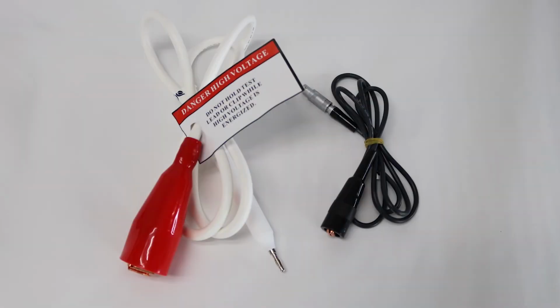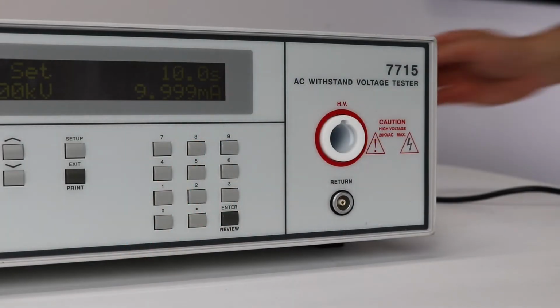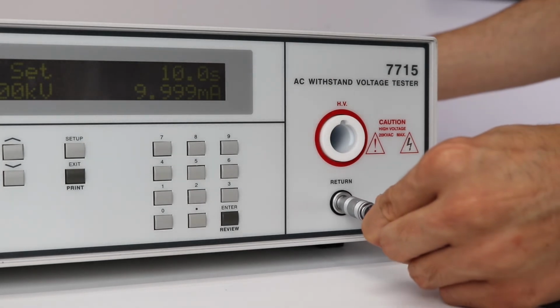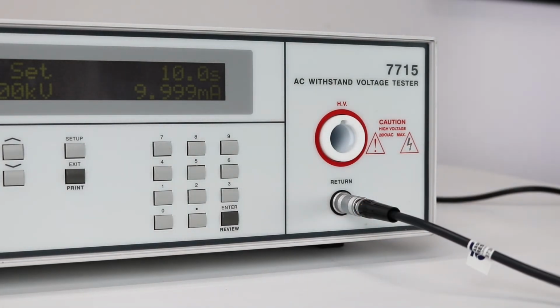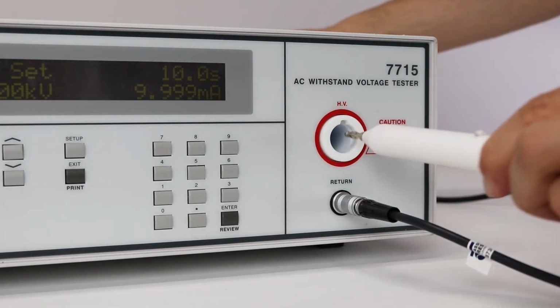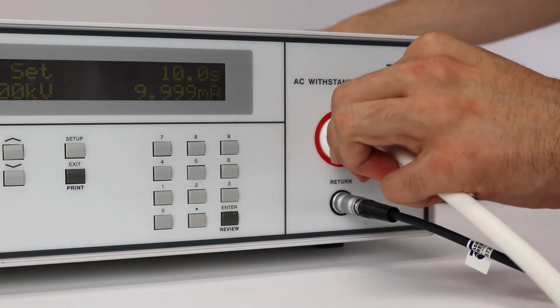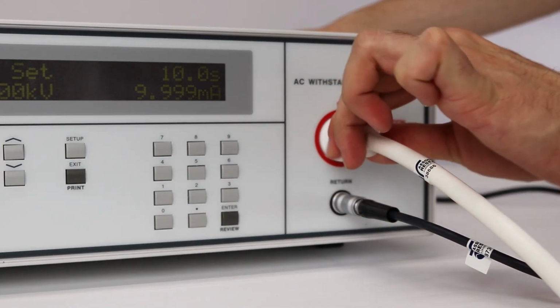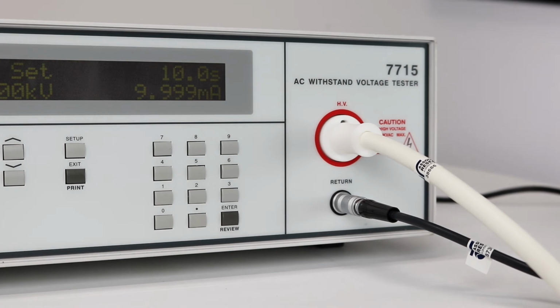To connect the HypotMAX to the DUT, you're going to need the following accessories: the red high voltage lead and the black clip return lead. First, connect the black lead to the return terminal on the HypotMAX. Connect the high voltage lead by plugging in the white Alden style connector to the HV terminal. Be sure to line up the plastic knob on the HV lead with the slot on the HV terminal on the HypotMAX. Once inserted, turn clockwise and lock the lead into place.